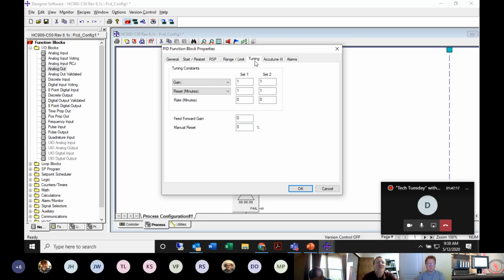Tuning. Tuning is the next tab. So in all UDCs, you get automatically 2 tuning sets. You can program additional tuning sets in an HC900, but out of the box, you get 2 tuning sets. I can choose proportional band or gain, reset or resets per minute or repeats per minute. Rate. You can choose, and then you go over and you program what each one of those are going to be based on how you're tuning the process.